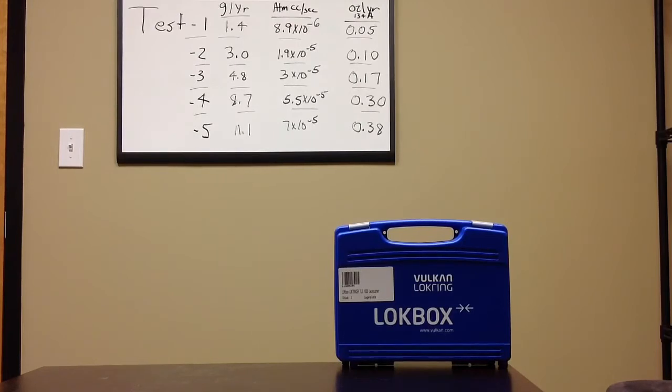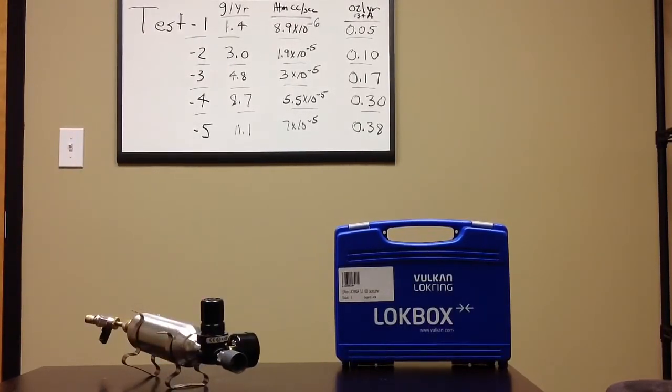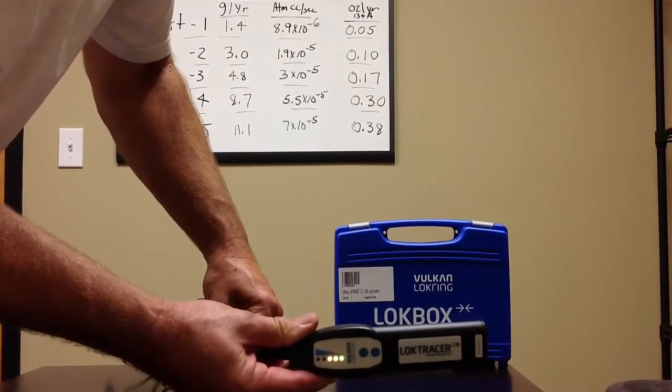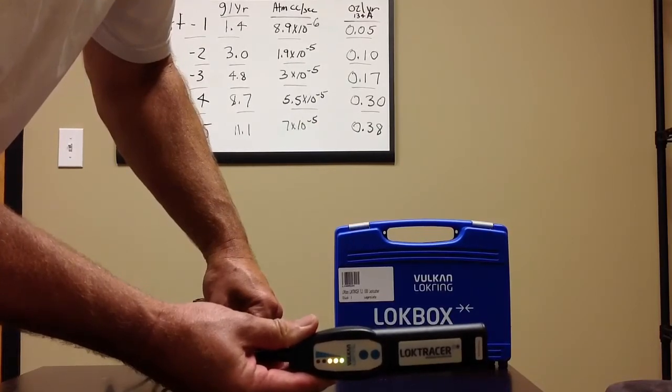Third test point, 4.8 grams per year, 0.17 ounces per year. Expose the leak to that. Strong response there.